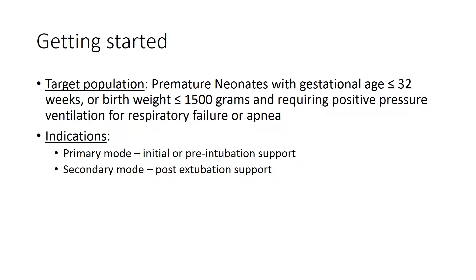When initiating NIPPV, your starting settings will differ based on whether you are using NIPPV as a primary or secondary mode of respiratory support. In the primary mode, your PIP will be somewhere between 20 and 25. Your PEEP will be between 5 or 6, and your rate will be somewhere between 20 and 30. Due to the non-invasive delivery of pressures, your I time will always be 0.5. Your FiO2 will be adjusted to maintain your targeted goal oxygen saturations.